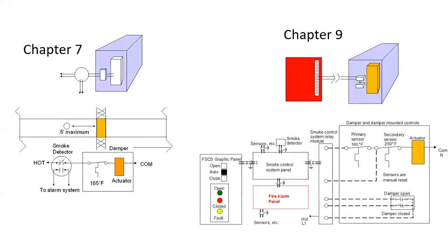Next. So there's Chapter 7 on the left. The controls are a smoke detector within 5 feet of the damper. And then you'll have a high temperature limit, typically 165 degree, 90% of the time. And then your actuator. And if you detect either smoke or you get an elevated temperature in the duct, the actuator power is cut, and it springs the damper closed. Chapter 9 are going to be a lot more complex in most cases.